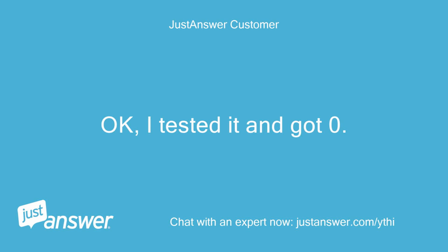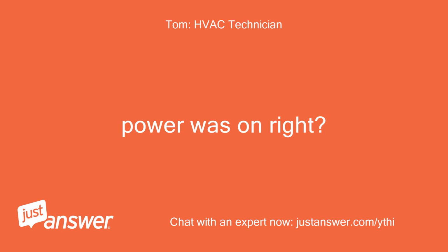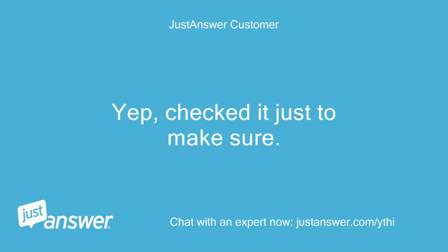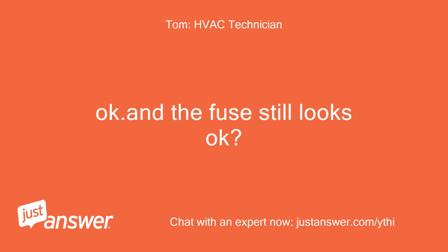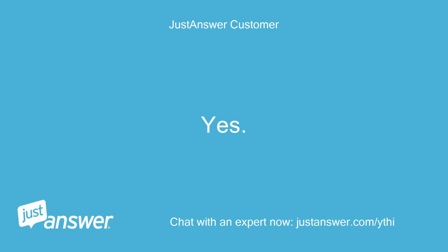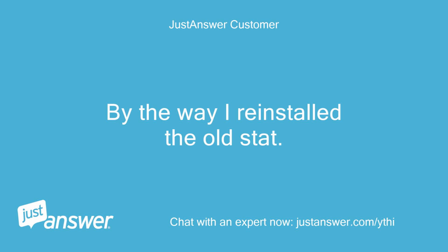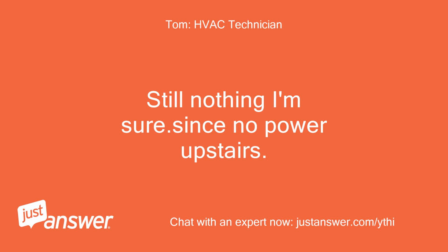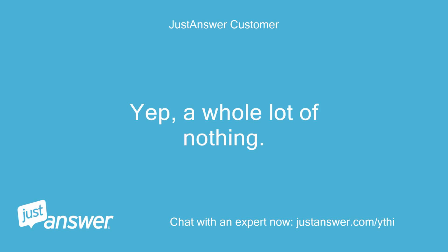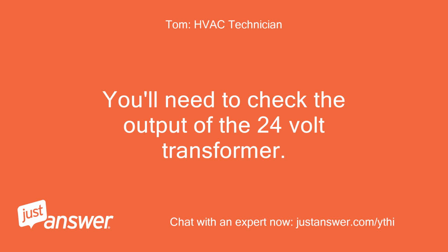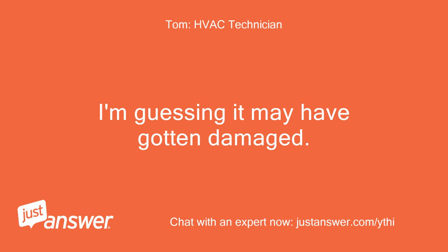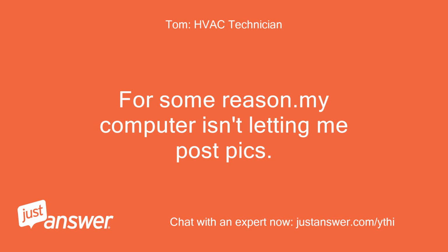Okay, I tested it and got 0. Power was on, right? Yep, checked it just to make sure. Okay. And the fuse still looks okay? Yes. By the way, I reinstalled the old stat. Still nothing, I'm sure. Since no power upstairs. Yep, a whole lot of nothing. You'll need to check the output of the 24 volt transformer. I'm guessing it may have gotten damaged. For some reason. My computer isn't letting me post pics.